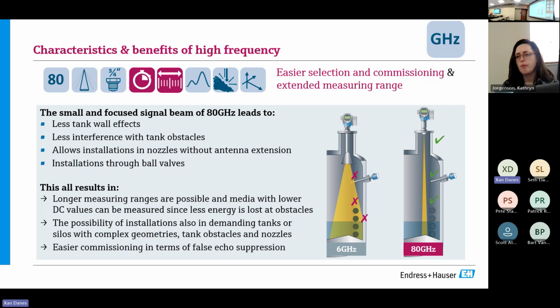From a technician standpoint, if you're worried about false echo suppression or locking onto false signals in the tank, it can make commissioning quite a bit simpler too, since you're seeing less noise, less tank geometry, and mostly just shooting off the product itself.